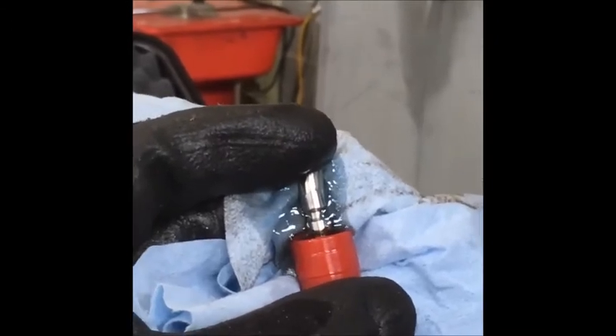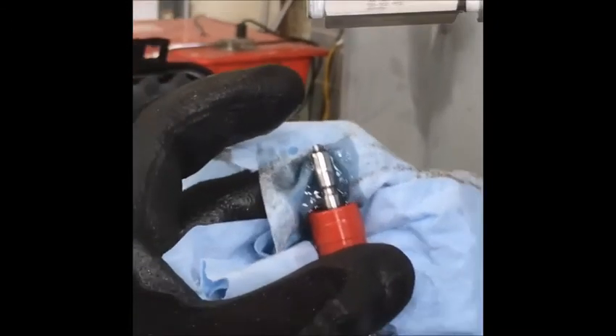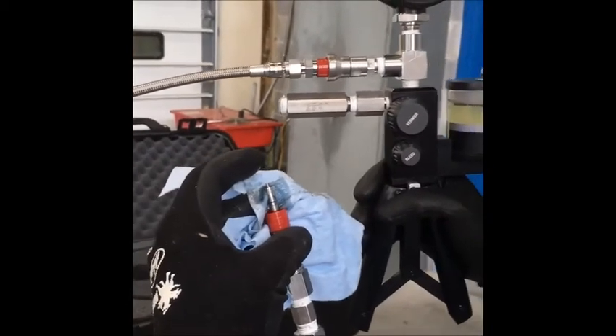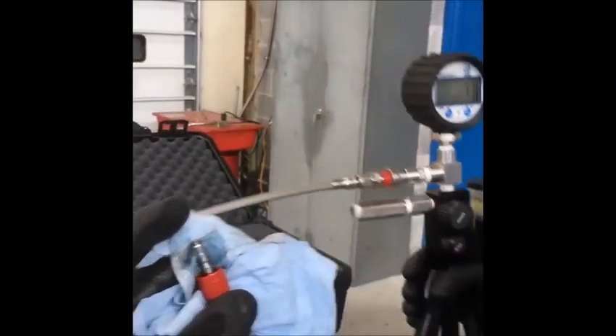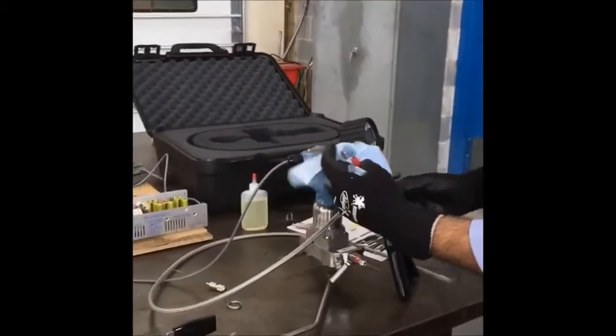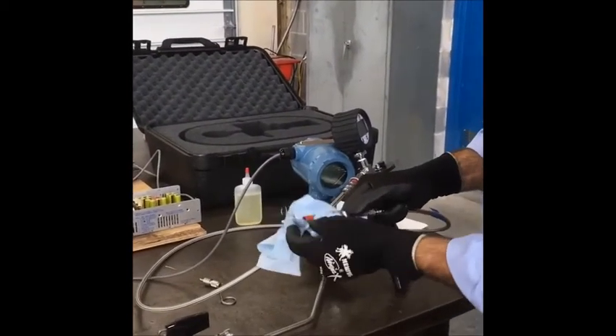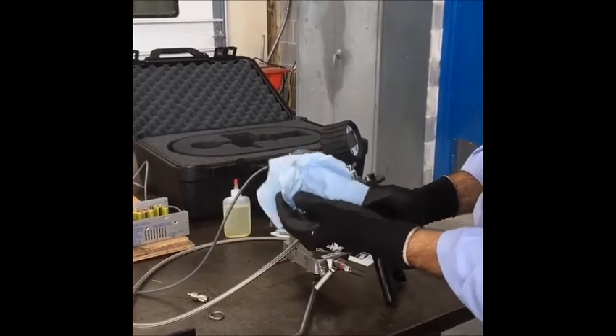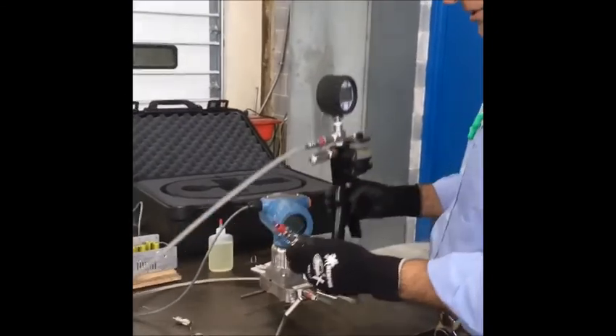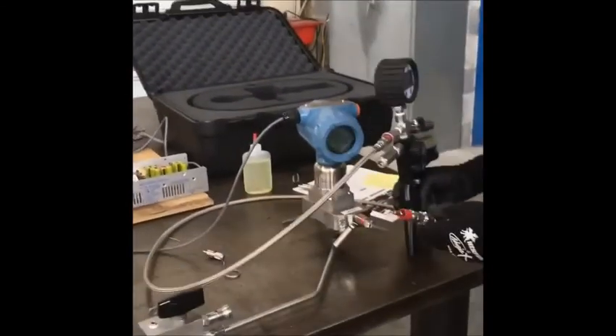Okay, and I'm going to say that's probably enough. And then I can release the button and that will trap the oil in the hose, and then we're ready to go. Then down here a second. Wipe a little bit of the oil off. Okay, at that point we're ready to plug our calibration pump into the test block.